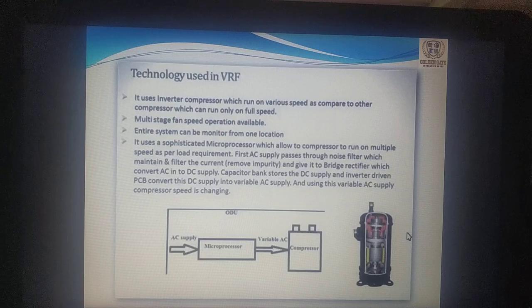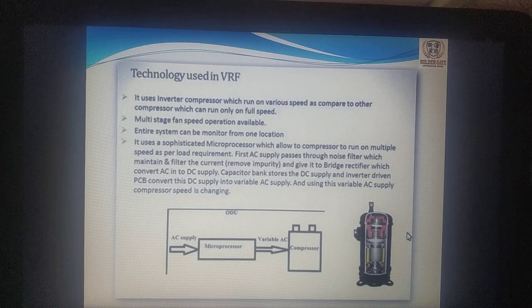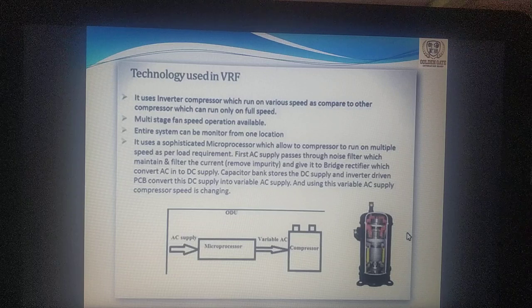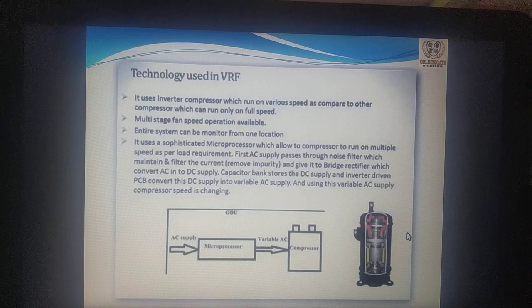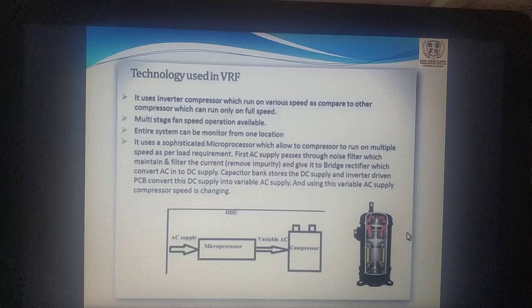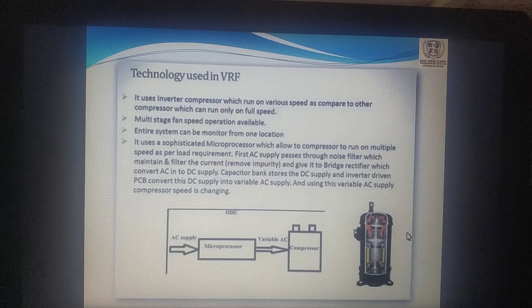First, AC supply passes through a noise filter which maintains and filters the current, removes impurities, and gives it to a bridge rectifier which converts AC into DC supply. A capacitor bank stores the DC supply, and the inverter-driven PCB converts this DC supply into variable AC supply. Using this variable AC supply, the compressor speed is changed according to the load.